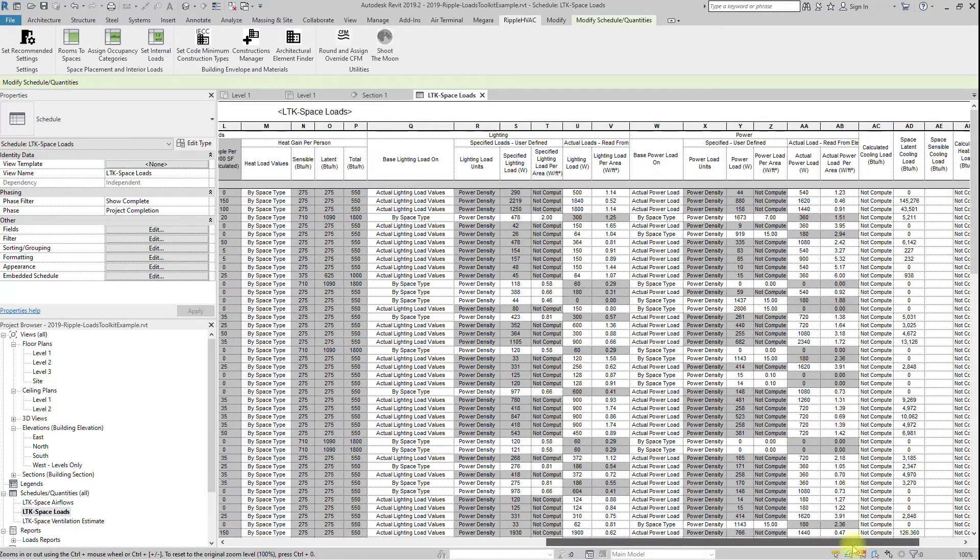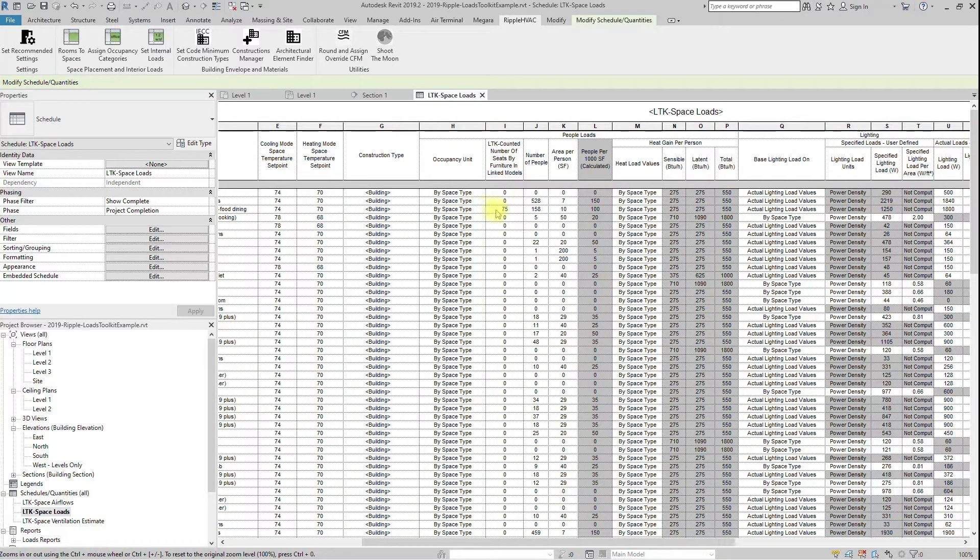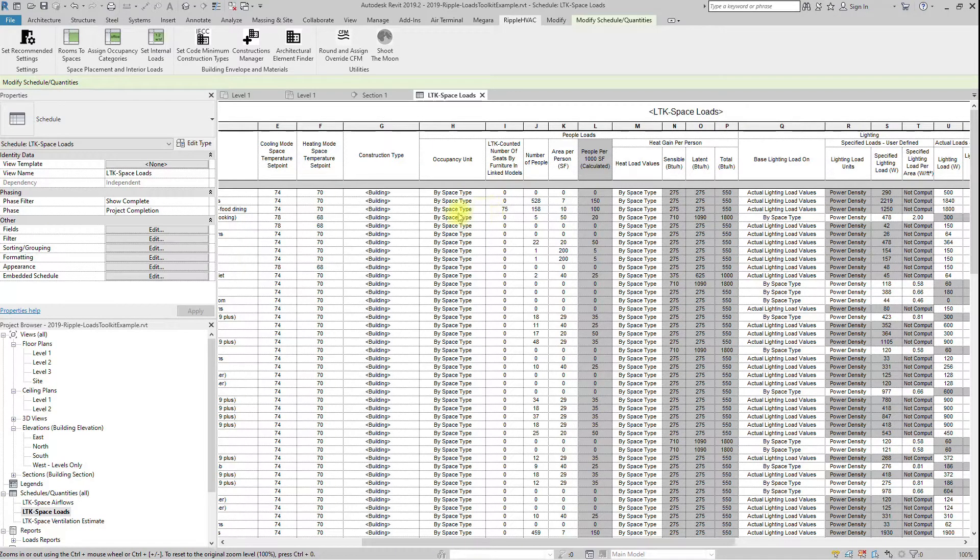By default, Revit has no actual people count for spaces. The internal loads assistant button attempts to count the amount of people in the space by examining all of the furniture in the space and adding up all of the seats to get a people count.